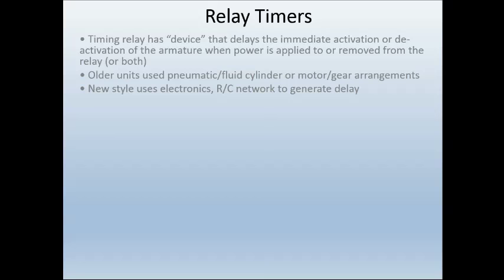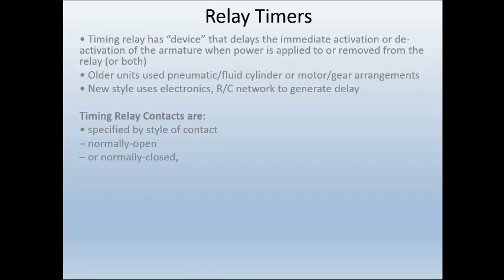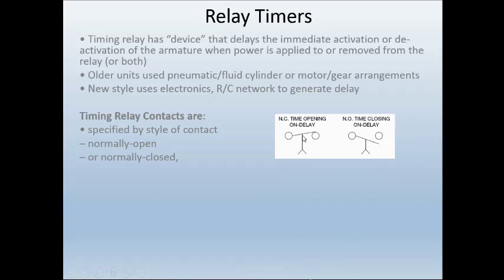The older units used for timing relays use pneumatics and fluid cylinders or gear or motor arrangements — like a watch — to do the timing. New styles use electronics and RC networks to generate the delay. With ladder logic, we're going to use the timer instruction and that's how we're going to create our delay.